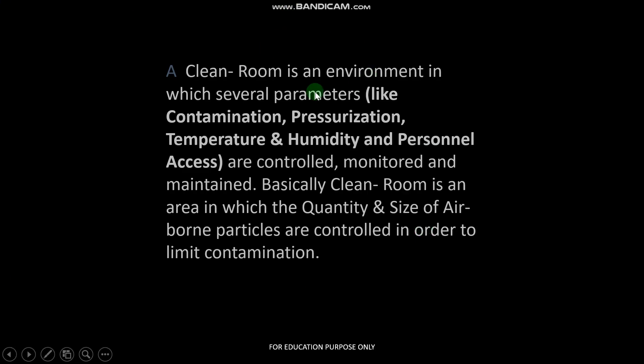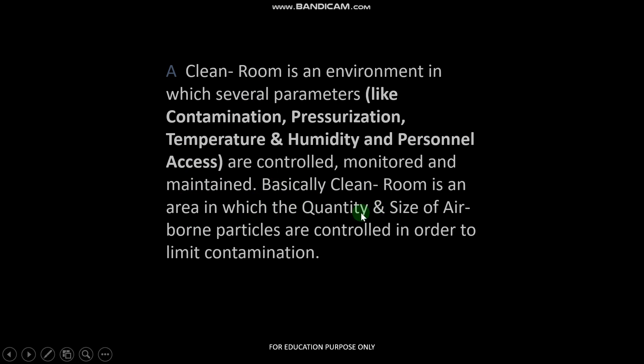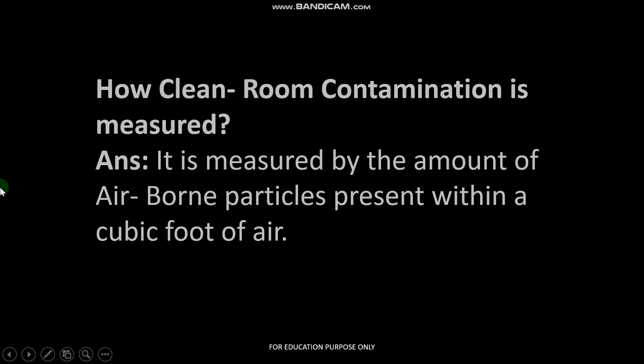A clean room is an environment in which several parameters — including contamination, pressurization, temperature, humidity, and personnel access — are controlled, monitored, and maintained. HEPA filters are used in industry to prevent contamination. Basically, a clean room is an area in which the quantity and size of airborne particles are controlled in order to limit contamination. Clean room contamination is measured by the amount of airborne particles present within a cubic foot of air, and particles are measured in microns.